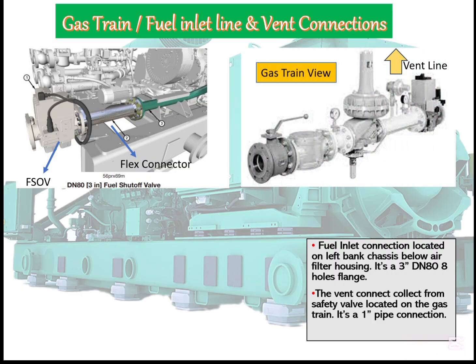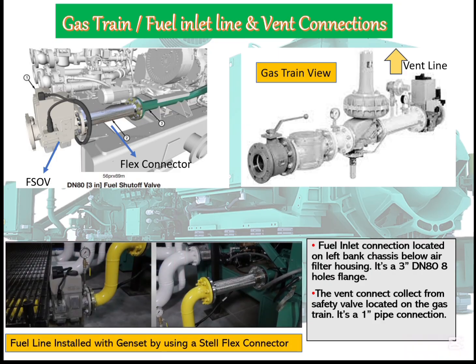Let's have a look at the gas train. After this FSOV, we have the gas train, where we have a pressure regulator, fuel filter, and the valve or manual valve. So the connection is where the customer has gas availability, the 3-inch line, and it is connected to this valve. This is the fuel inlet line entering the genset. Then we also have a vent line in case of overpressure, normally a 1-inch pipeline. We take a 1-inch pipe from here and release it in the air. In case the pressure regulator stops working or becomes faulty, the overpressure will evaporate and throw the excess gas into the air.